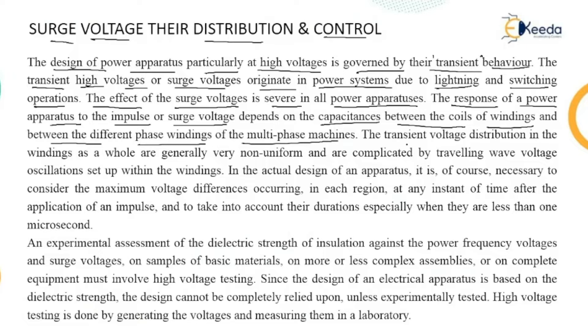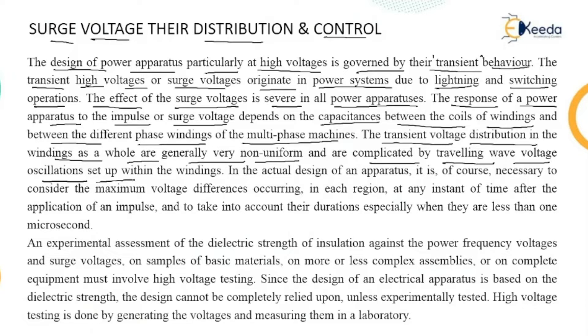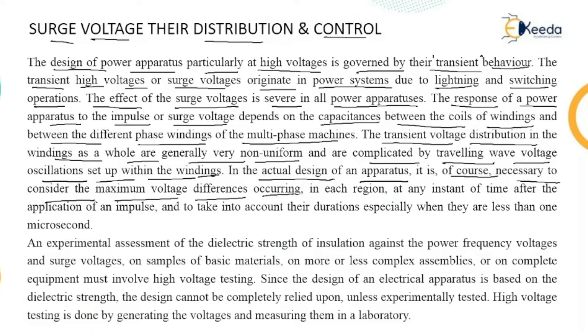The capacitances developed basically decide the response of a power apparatus. The transient voltage distribution in the windings as a whole is generally very non-uniform and is complicated by traveling wave voltage oscillations set up within the windings. These traveling waves travel on the lines and set up voltage oscillations within the windings.